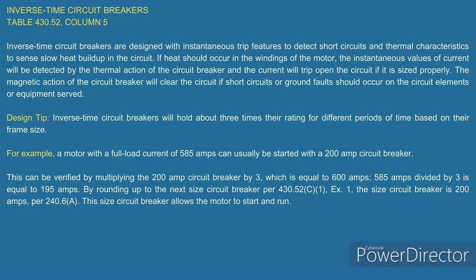And when you start looking at these inverse time circuit breakers, they'll hold about 3 times the rating, and they hold them for different periods of time. But the reason for that is it's all based on the frame size. And that's what I was saying in the last illustration. I was talking about the frame size being 150 amps for that instantaneous trip circuit breaker. The frame size is going to determine what that holding amps is going to be, and then you've got your different values that you use to see if it'll hold that locked rotor current of that motor.